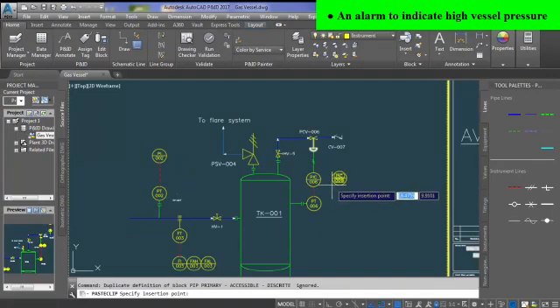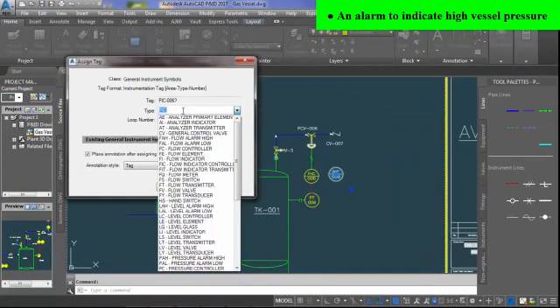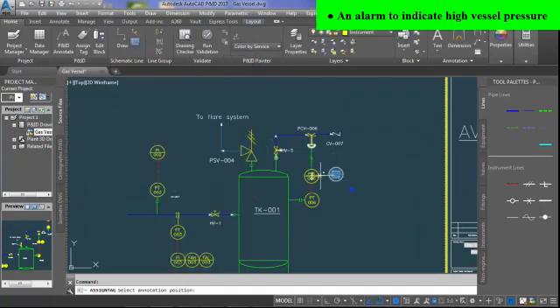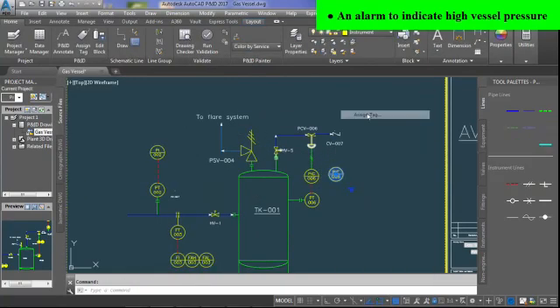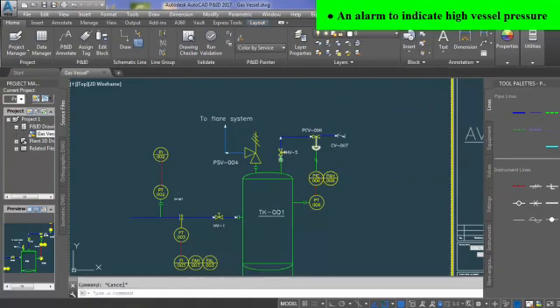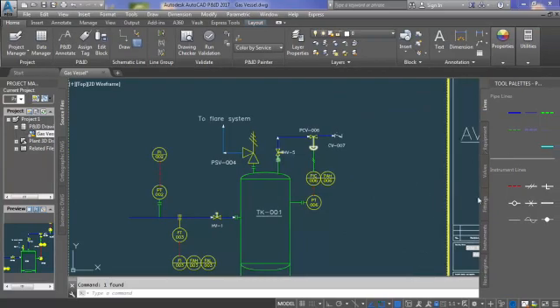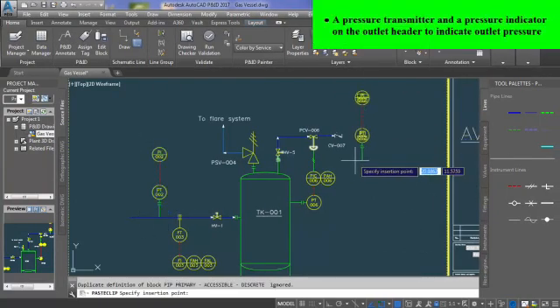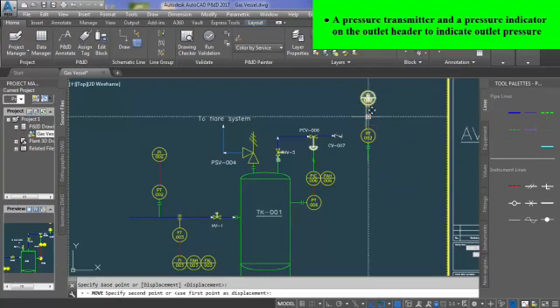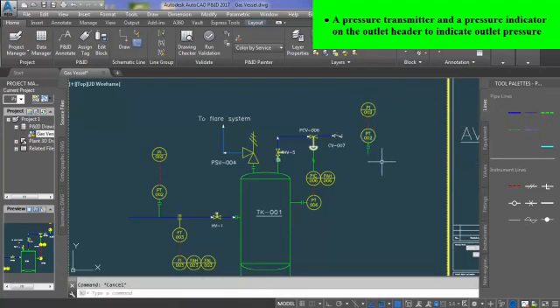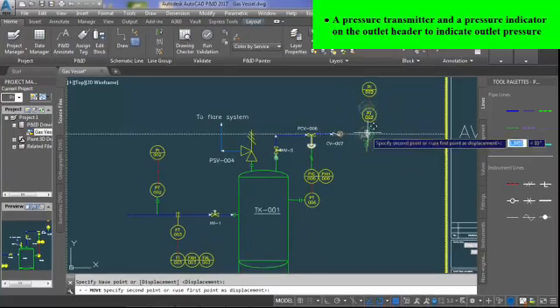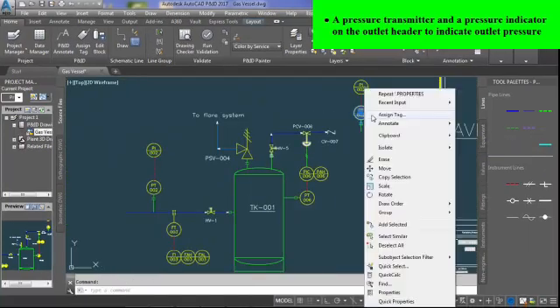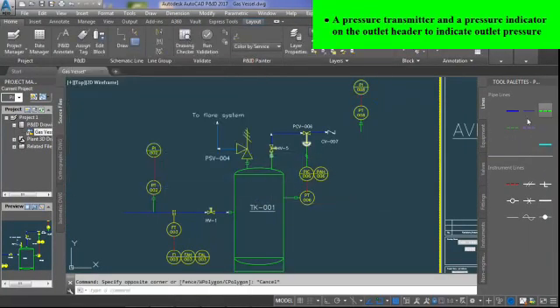A high pressure alarm is also added with the pressure indicator controller. Lastly, pressure transmitter and pressure indicator are provided to measure and indicate gas outlet pressure. On the P&ID, PT-8 and PI-8 are performing this function.